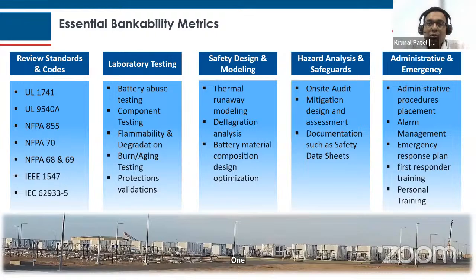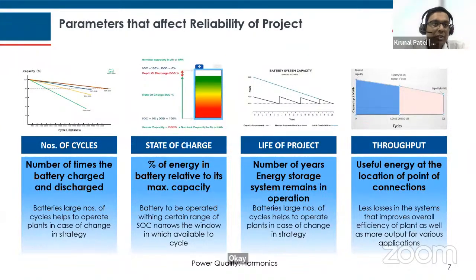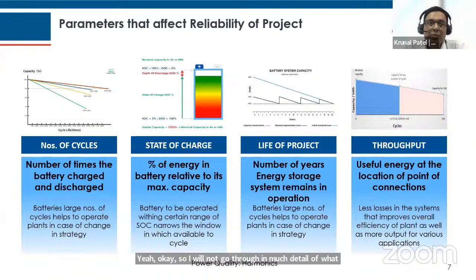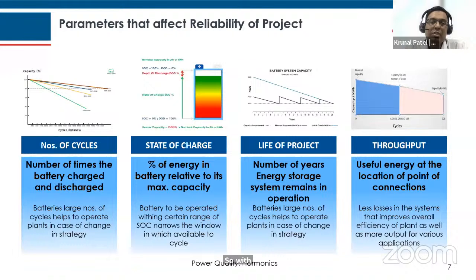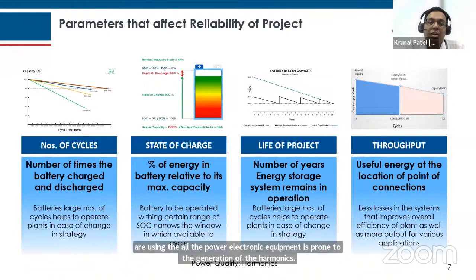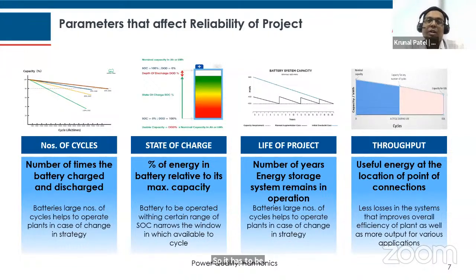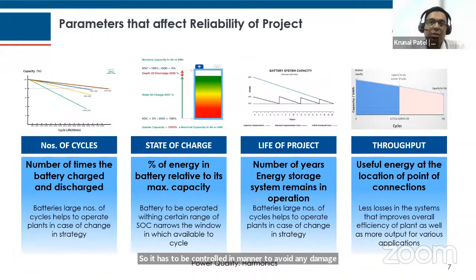Yeah, okay. So I will not go through all the parameters in much detail. Moving further to the parameters that really affect the reliability of the project, there are 4 parameters we identify: number of cycles, state of charge, life of project, and the throughput output of energy from the battery energy storage system. With that, one more which is very important is power quality, because all the power electronics equipment we are using is prone to the generation of harmonics, so it has to be controlled to avoid any damage to all other equipment connected to the grid. So these are the major 4 points which affect the overall reliability of the plant throughout the life of the project.